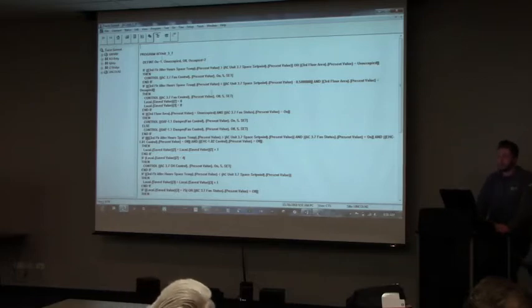So this is controlling AC Unit 3-7. You have your definitions right here, like I said: integer, so on equals 1, unoccupied equals whatever it would be. I don't know if that's 2 or whatever. It's off, it's 0. 0 is for unoccupied, so off is 0, occupied equals 2, so it kind of gives you what it's going through. If there's no equal sign after the variable, that means it's a 0. Okay, gotcha.